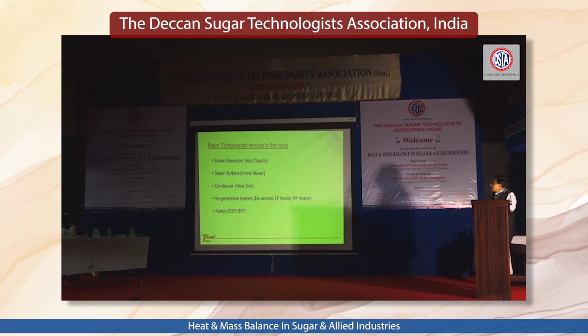In any cogen plant, the major components of the TG island are the steam generator, which is the boiler we are all familiar with; the steam turbine, which is the prime mover; the condenser, which acts as a heat sink for a condensing turbine; and the regenerative heaters, deaerators, LP heater and HP heater. We take almost 4 extractions from the turbine: one for process at 2.5 ATA, and three others to improve the heat rate of the power plant. Pumps such as the condensate pump and boiler feed water pump are also required to complete the cycle.